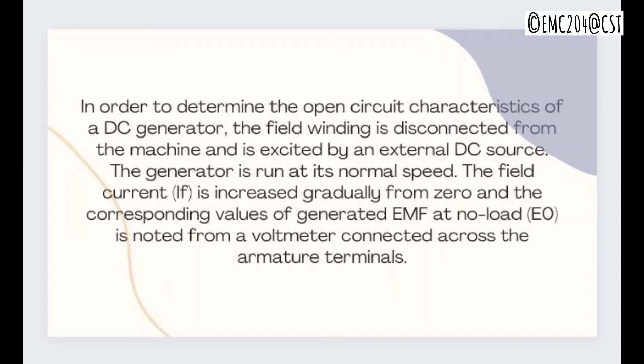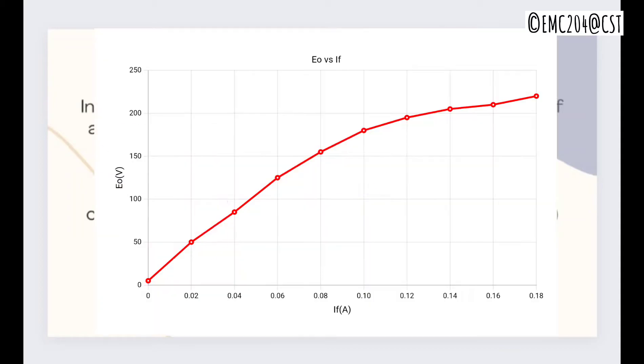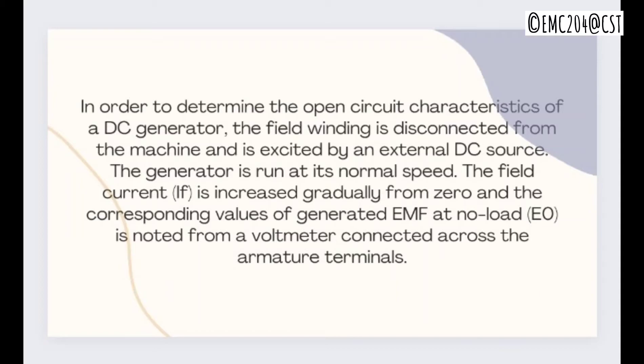From the EMF equation of a DC generator, the generated EMF should be directly proportional to the field flux. However, even when the field current is zero, some amount of EMF is generated. As you can see from the figure, this initially induced EMF is due to residual magnetism in the field poles. Due to this residual magnetism, a small initial EMF is induced in the armature, which aids the existing residual flux and hence increases the overall field flux, leading to an increase in induced EMF.